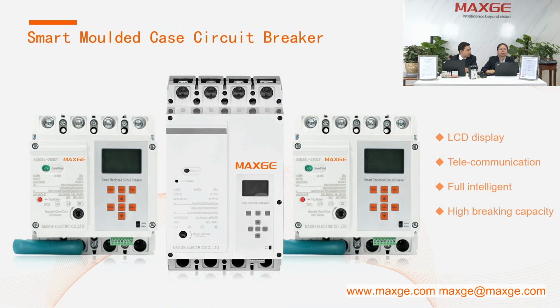Now the next type of the MCCB is our smart MCCB. Smart MCCB, we have the LCD display. Here it is very beautiful, also with telecommunication and intelligent functions. Also it is with high breaking capacity. Yes. The frame is from 125 to 630. And the protections which the smart molded case circuit breaker offers are overload protection, then short circuit protection, earth leakage protection, over voltage protection, under voltage protection, then also it gives the earth leakage protection also.